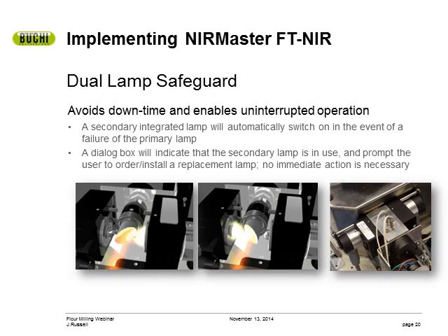One of the features about the Buchi NIRMaster that flour millers really like is that it has two lamps — a primary lamp and a secondary lamp. When the primary lamp burns out or loses intensity, the secondary lamp automatically kicks in. You will not need to worry about checking your bias when this happens, nor when you replace the primary lamp — it is all perfectly aligned and the intensity is identical. Changing the lamp is super easy; it may take you five minutes at the most.